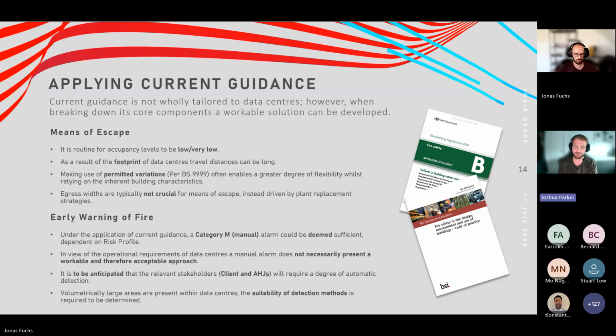But looking at the means of escape, the life safety aspects of design, taken away from property protection for a moment, we often find that these buildings have an incredibly low occupancy. Although a data center may have a significant footprint of tens of thousands of square meters, more often than not the occupancy is far less than 100 occupants, and that is often split over shifts as well. These buildings operate on a 24/7 basis, but we typically see anywhere between 40 and 70 occupants on a permanent basis. So things like egress widths aren't as crucial within data centers, but should still be considered nonetheless. It often comes down to minimum requirements anyway.